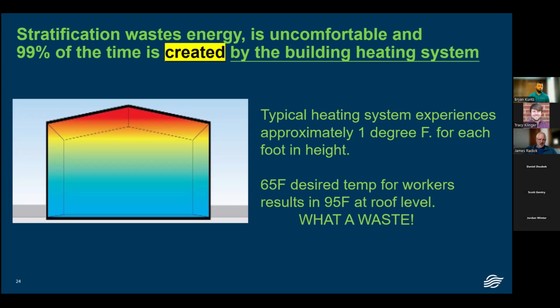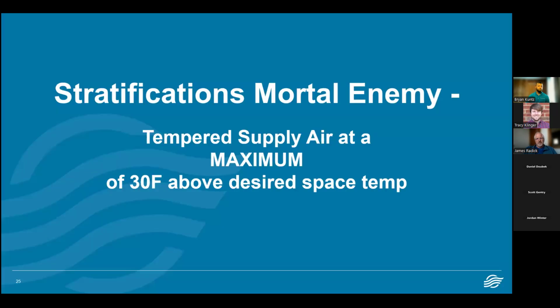So the illustration on the left does a great job of showing that if this is a 30-foot space and you've got 65 desired temperature for people at the floor, you could very easily get 95 degrees at the roof level. That's not doing anybody any good. It's just costing money. So it truly is a waste. Now, how do you combat stratification? It's a lot easier to deal with by just simply not creating it in the first place.